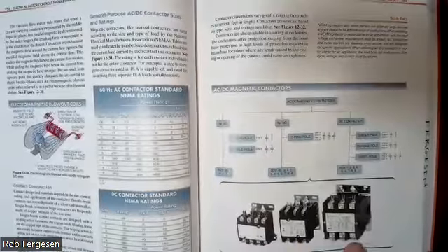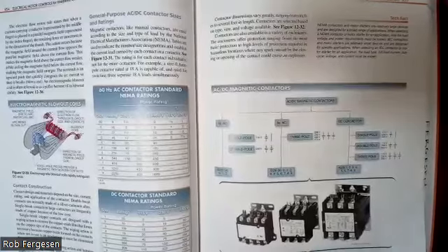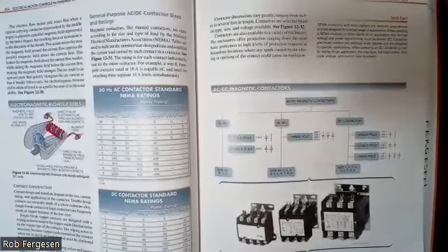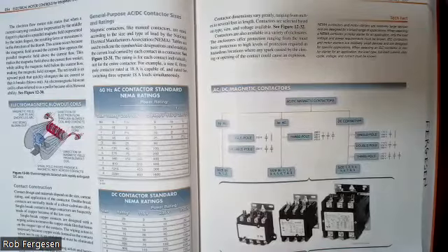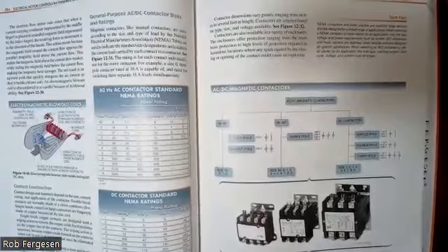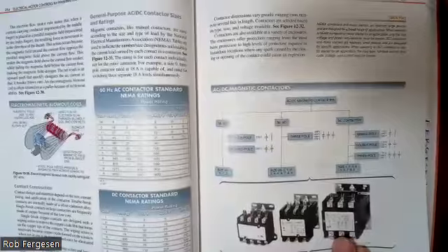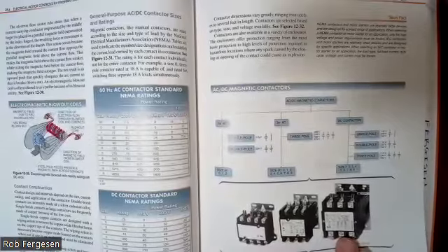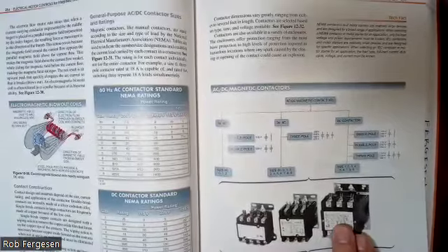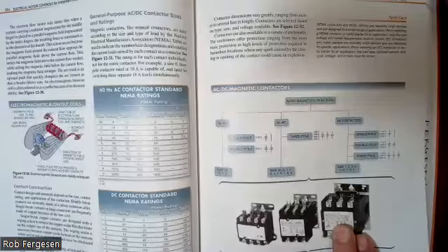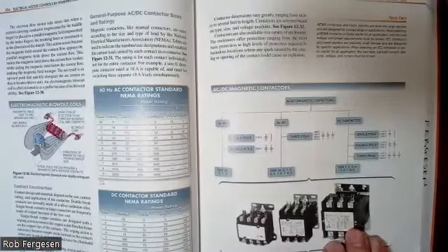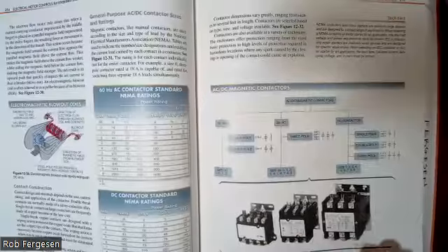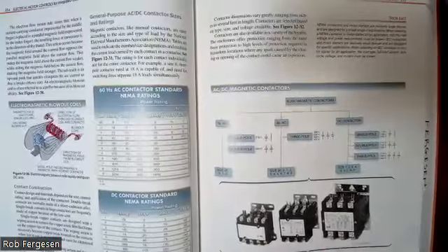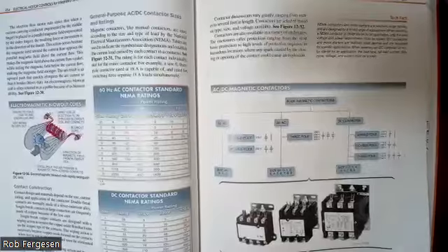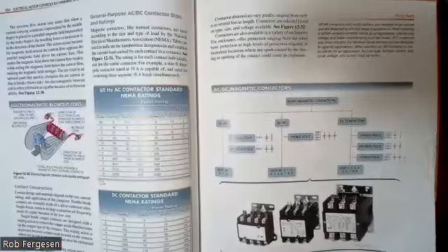These are 3 typical contactors. It comes in a range of sizes depending on what you're doing with them: single phase, 3-phase, or DC. DC contactors have to have slightly different construction. High power DC stuff is its own ball of wax. You always need to make sure that if you're using DC instead of AC, you've selected the right contactor for that. You can't just use the same. You've got to make sure it's rated properly.